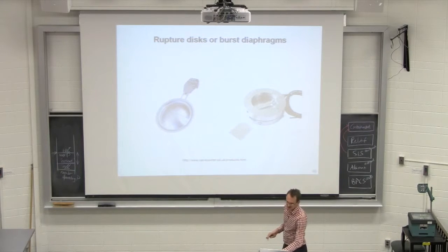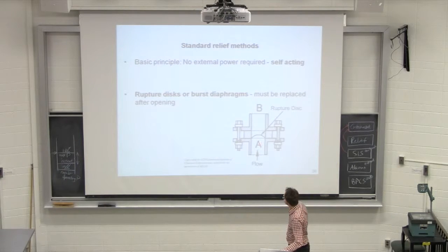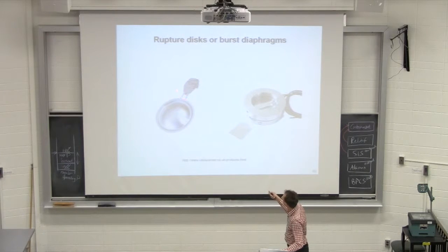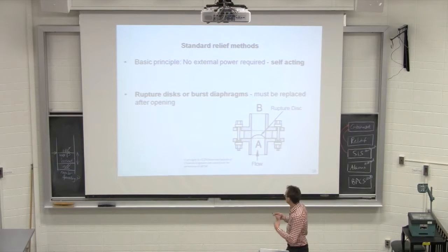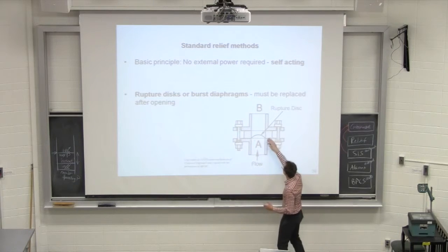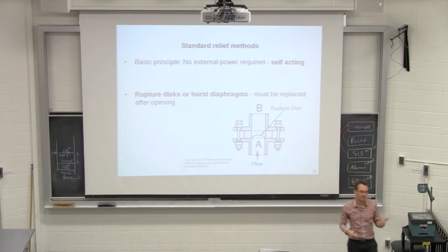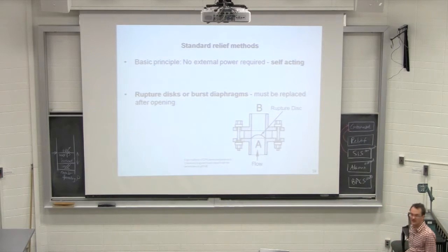When you buy them, it comes with this attachment that shows you the pressure rating for that diaphragm. When you put it in line, that label, that part that sticks out, protrudes outside the pipe so you can always see it and you always know what's inside your pipe. Once this is built, you can't see inside, but you see what the pressure rating is, and it will also tell you the direction, so you can always check that it was installed in the correct direction.